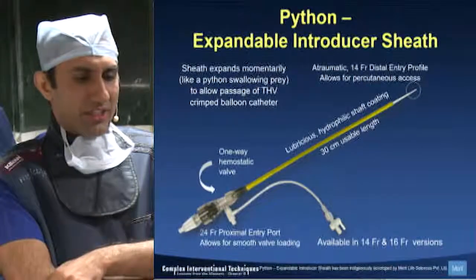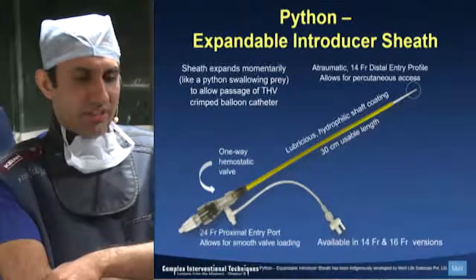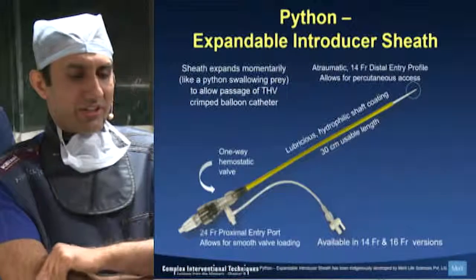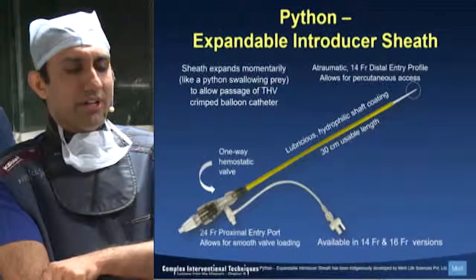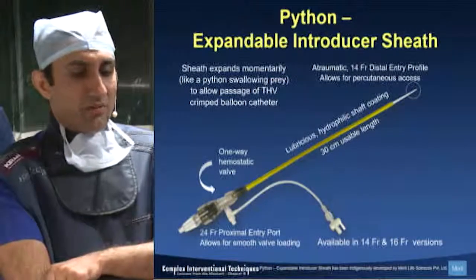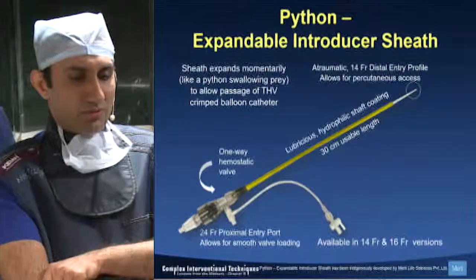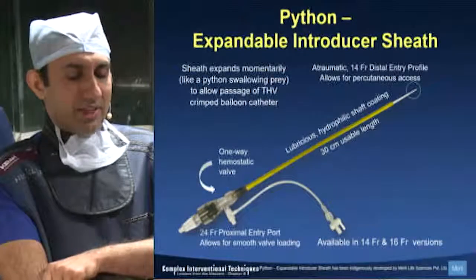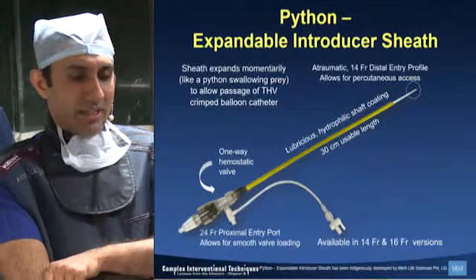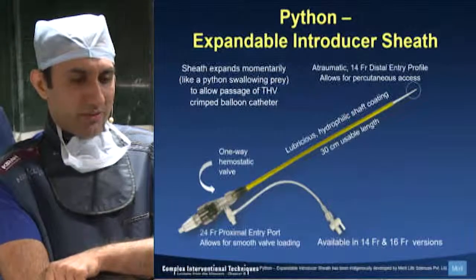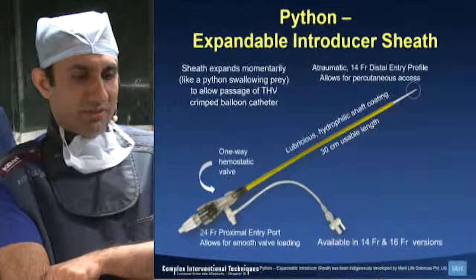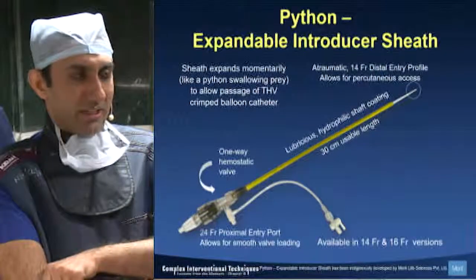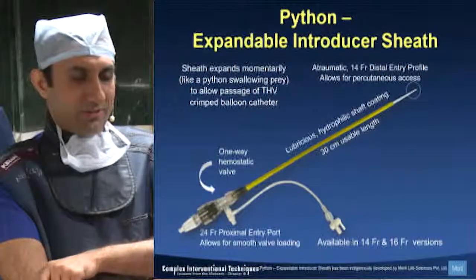This is the Python sheath. It is a hydrophilic sheath. It is a 14 French sheath and allows entry of the 22 French or 24 French profile of the valve when it is crimped over a balloon, and the sheath expands as the valve is being advanced, and it collapses back to its normal shape once the valve is in the abdominal aorta. Next slide.